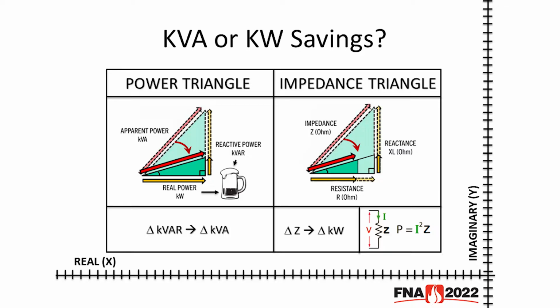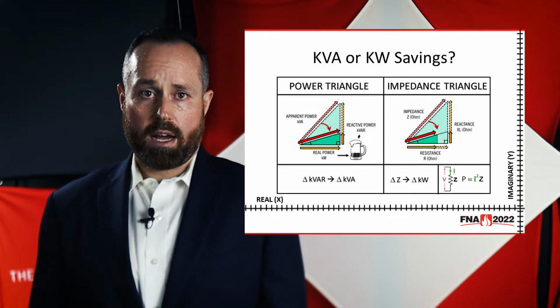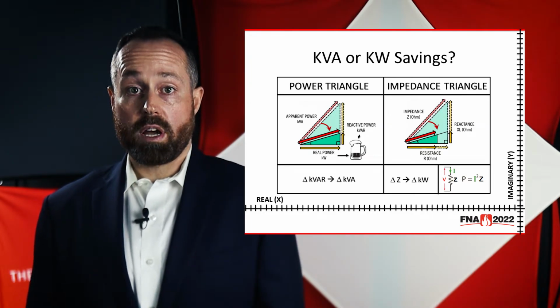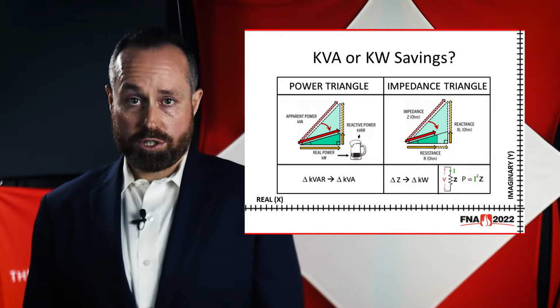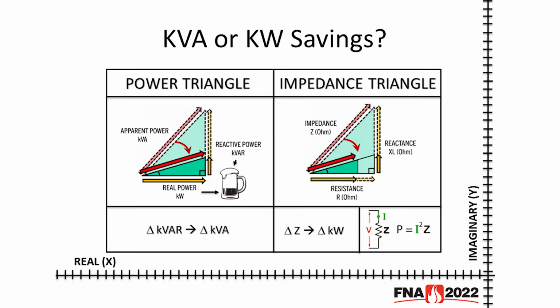Remember that kW is the power that is doing the actual work in the furnace, and accordingly will always be the largest component of power. This is the working power, and the objective is not to reduce kW to 0, but to reduce any unnecessary losses outside of the hot zone. This is accomplished through reductions in resistance and reactance, which is shown on the impedance triangle on the right. Similarly to the power triangle, the impedance triangle has real and reactive components, which are 90 degrees out of phase. The difference here is that the vectorial sum is now impedance, measured in ohms. Impedance reduction in a furnace circuit lowers kW demand.